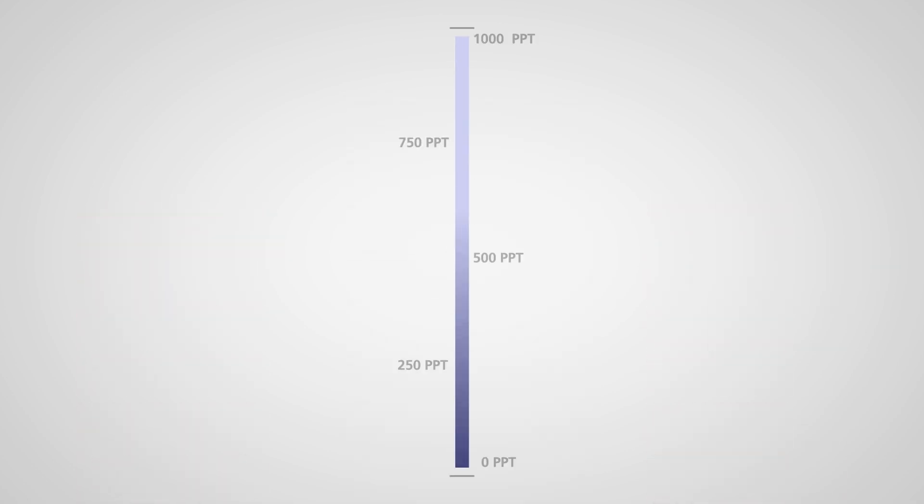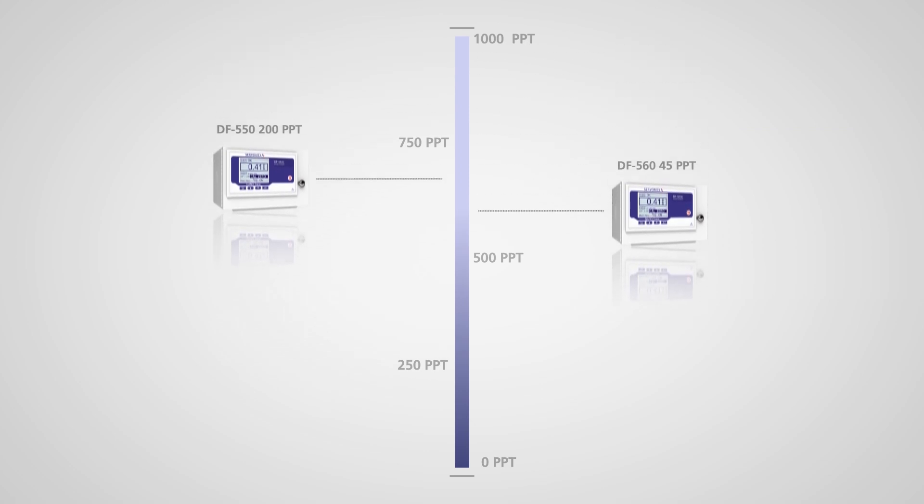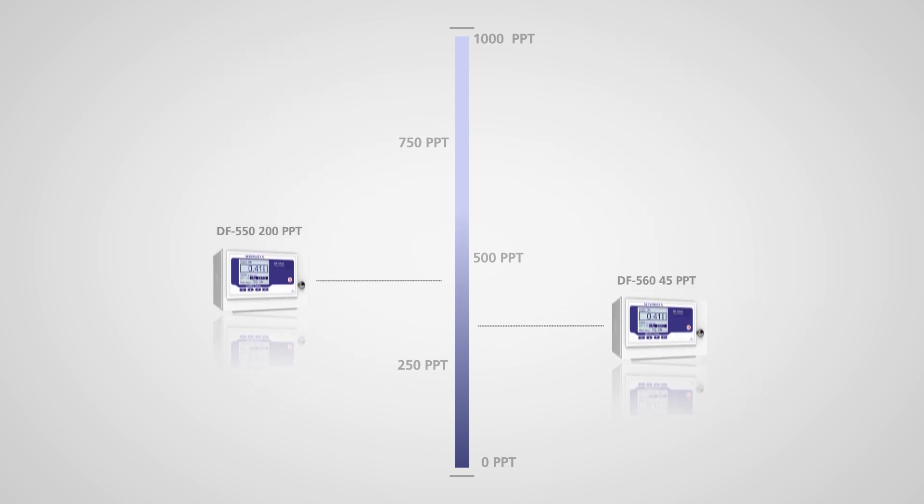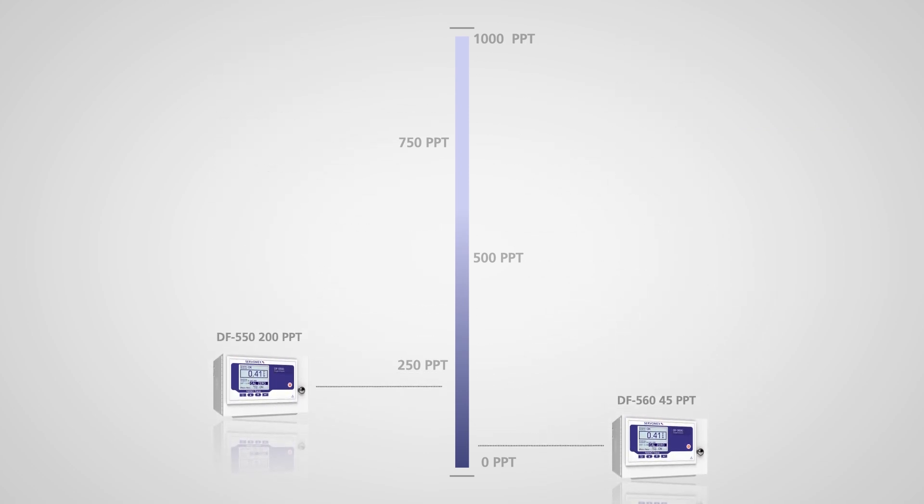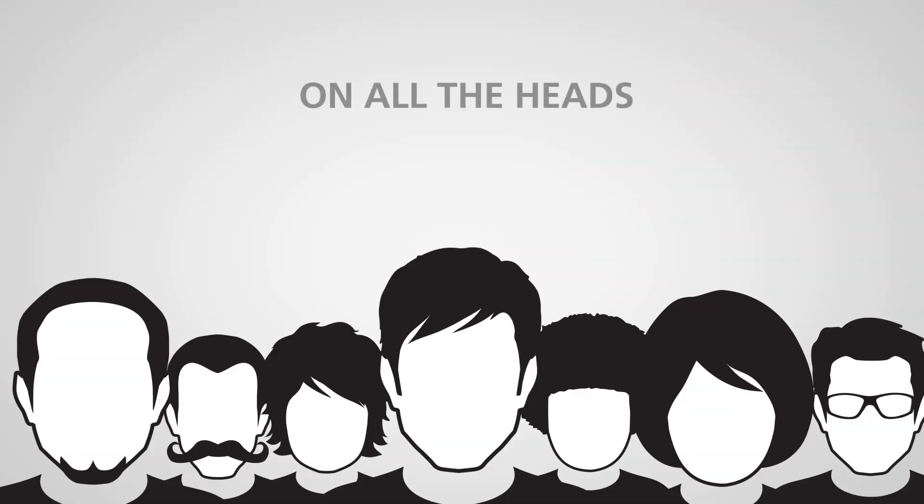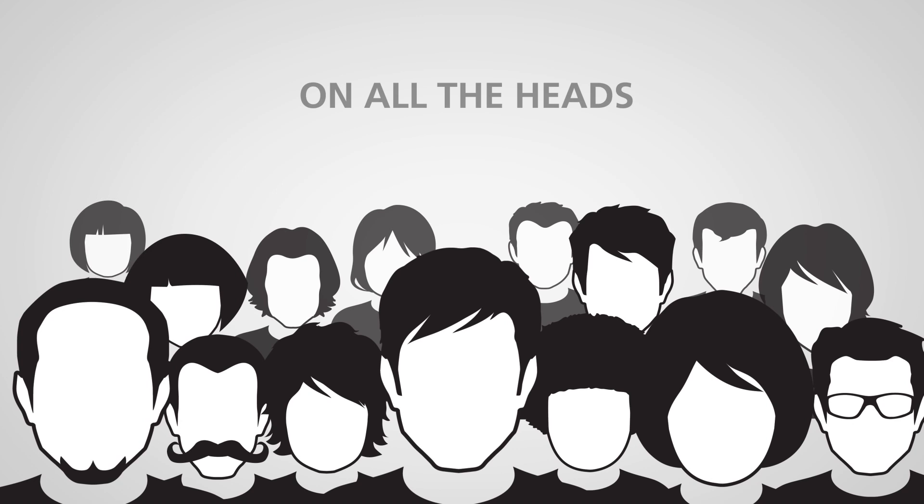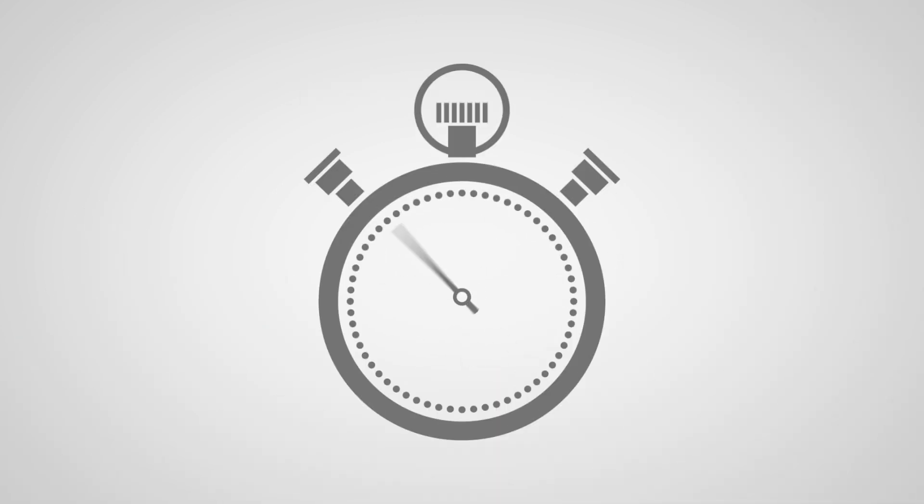DF500 analyzers offer the lowest detection levels available, right down to an incredible ultra-low oxygen measurement of just 45 parts per trillion. That's equivalent to finding just 45 hairs on all the heads of every single person in New York City in just seconds.